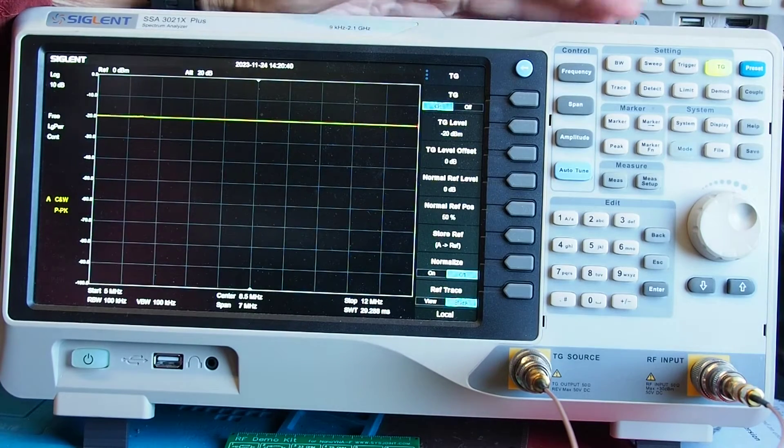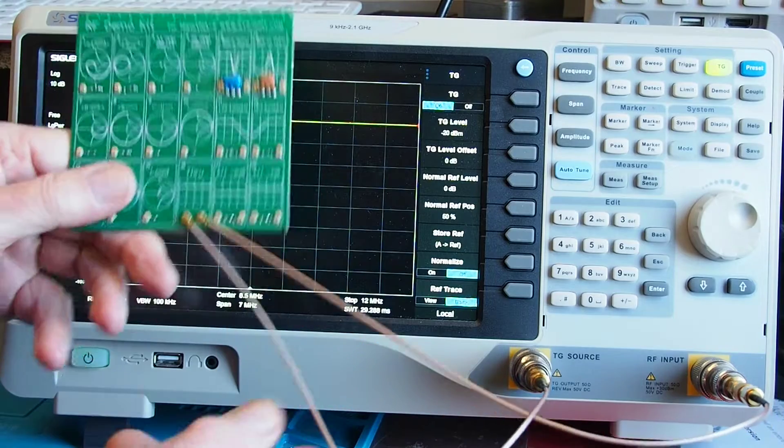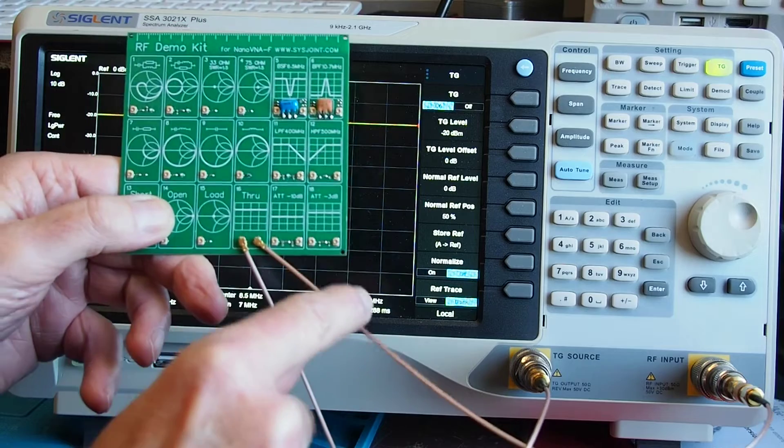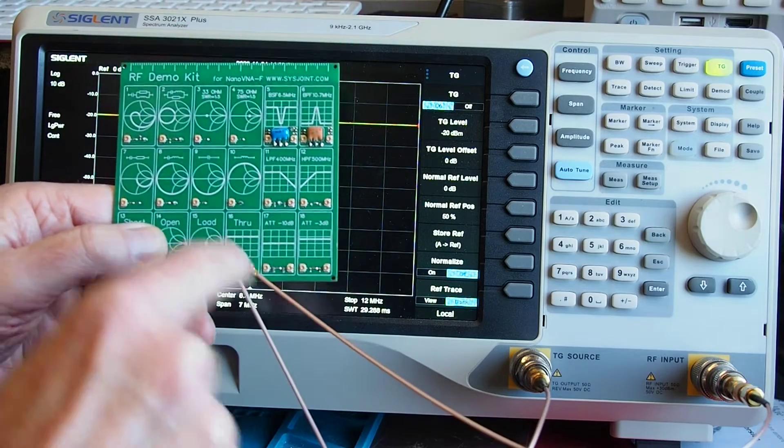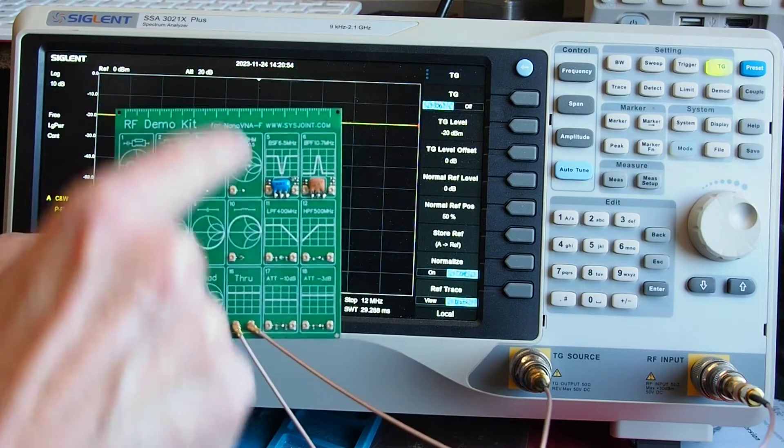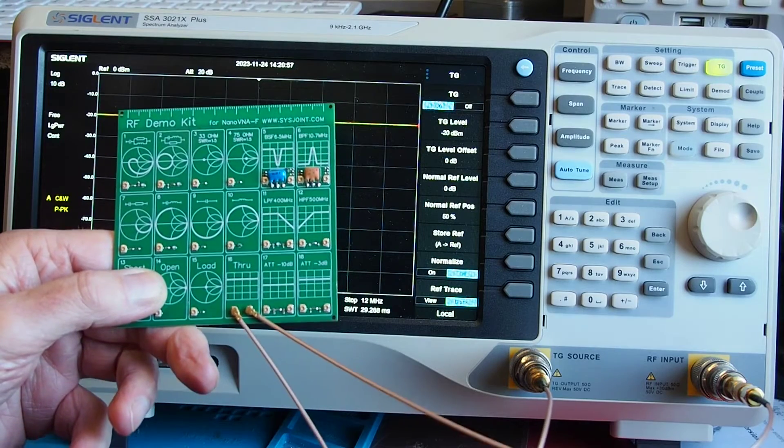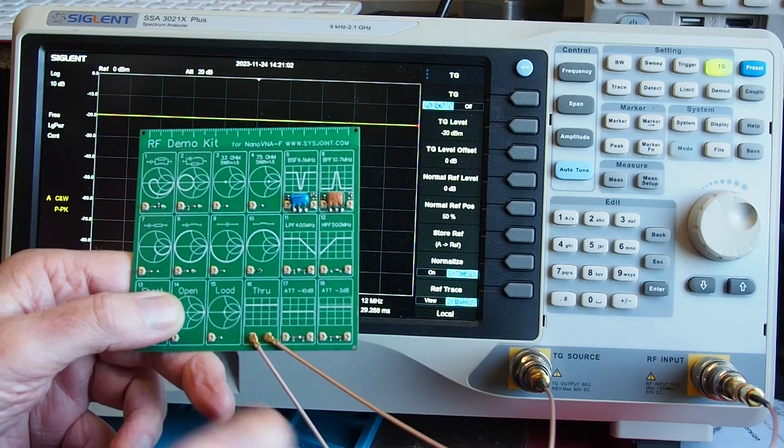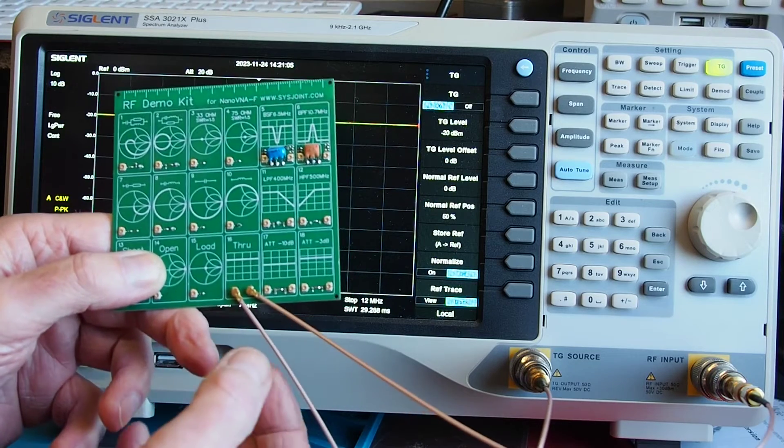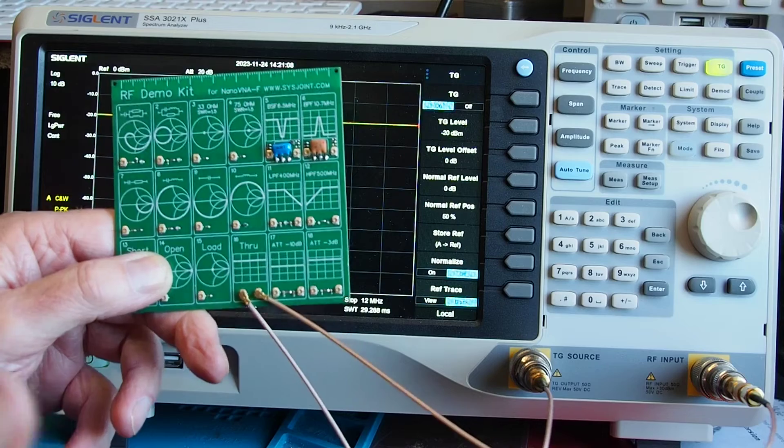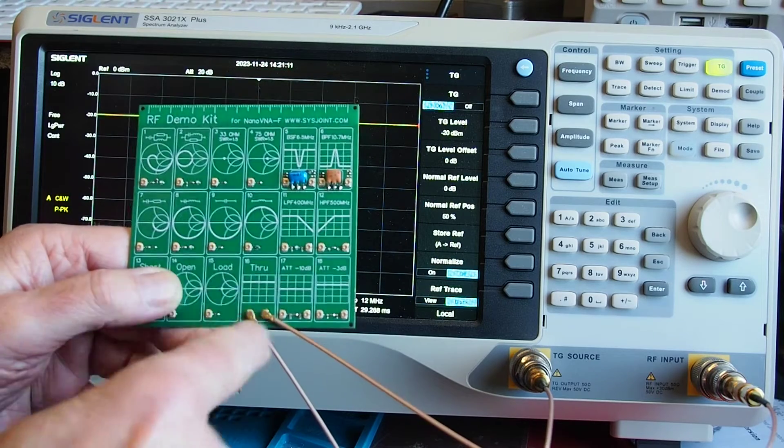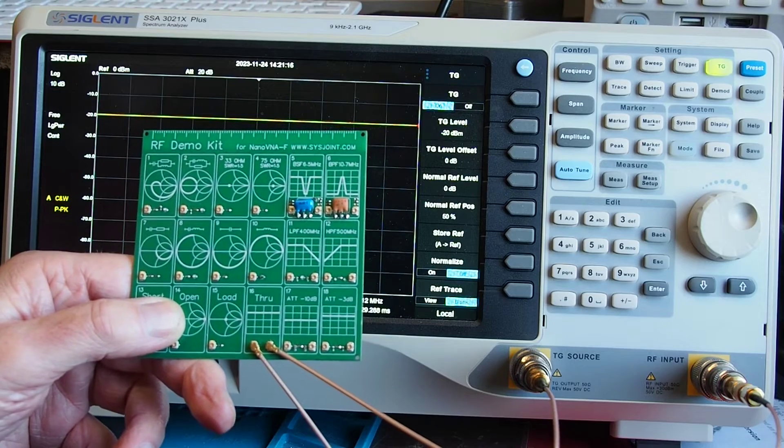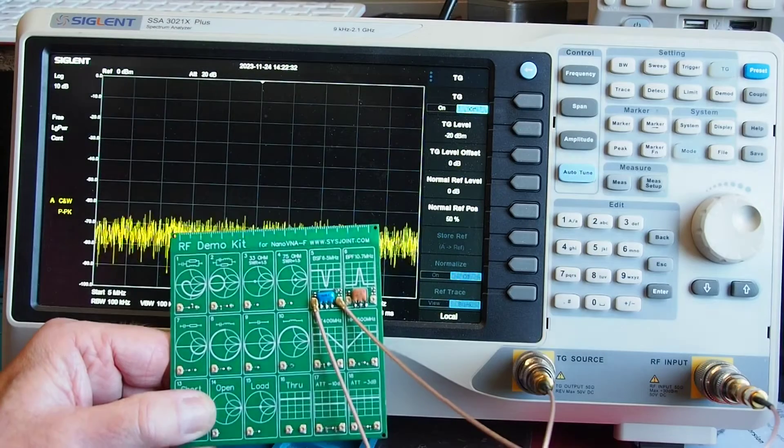But a point I want to make is that what I've got here I've got output of the tracking generator connected to input of the spectrum analyzer and by using the through connection on here I've actually allowed for anything which might be occurring in these two little fly leads as well so I've minimized the error if you like. I suppose another way to say it is I've actually included these cables in the calibration. So now what we'll do is we'll get them connected up to one of the filters and then we'll look at the kind of response we get.